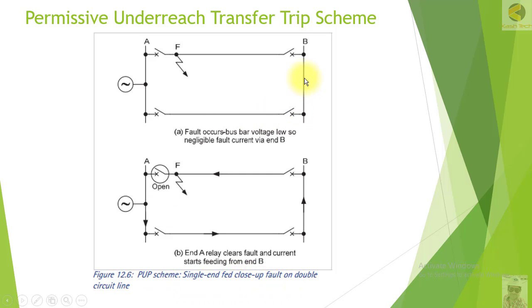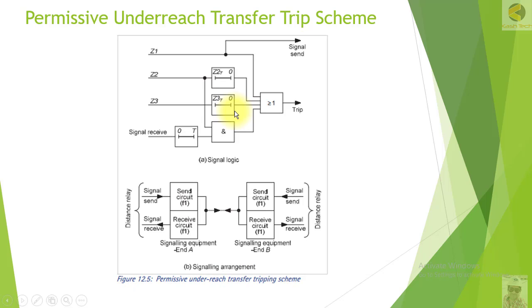This phenomenon normally occurs on double circuit lines. This is the logic diagram for the PUTT scheme. If there is a fault in Zone 1, the relay will trip the local breaker immediately through Zone 1 and will send a signal to the remote end.